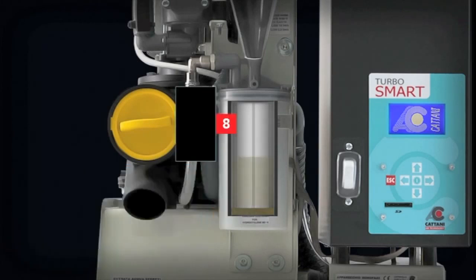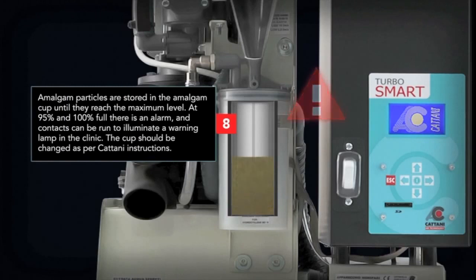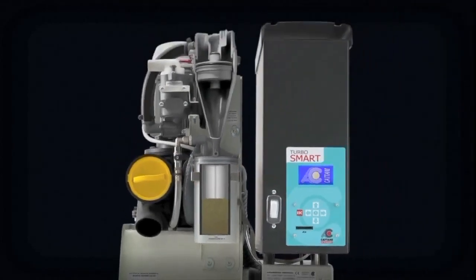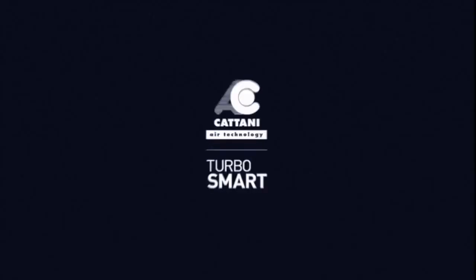Amalgam particles are stored in the amalgam pot until they reach the maximum level. At 95% and 100% full, the unit will alarm, notifying the user. When this happens, the amalgam pot should either be replaced for a new one, or alternatively, you can empty it into your sludge drum. Clean the pot thoroughly and replace. This should be carried out as soon as possible.